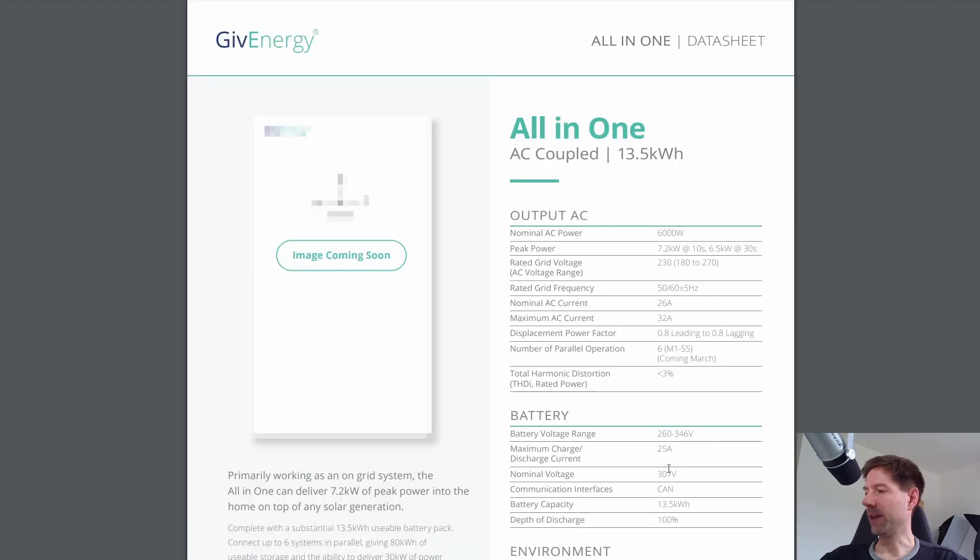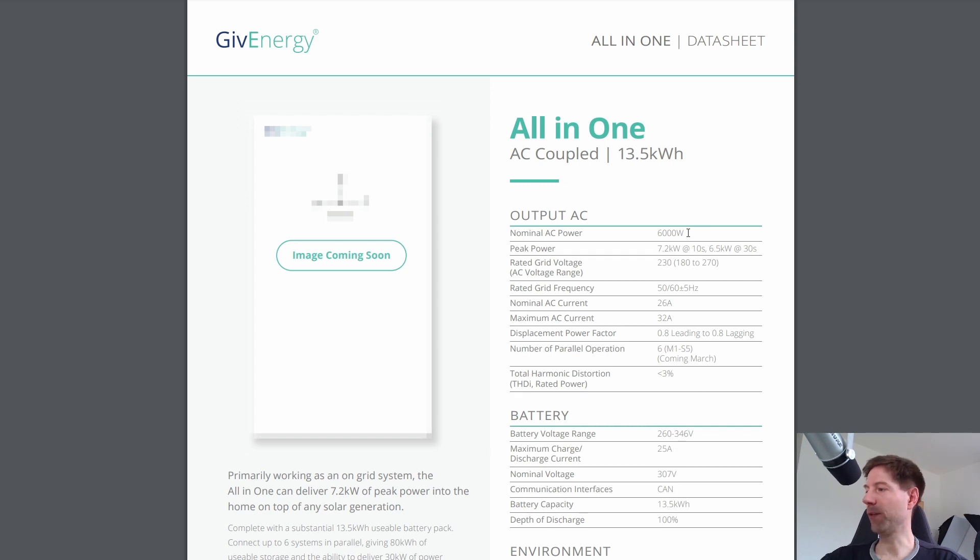Yes, the maximum charge and discharge current is the same at 25 amps, which equates to the six kilowatts. So you've got a slightly higher charging rate for the all-in-one battery, it looks like.